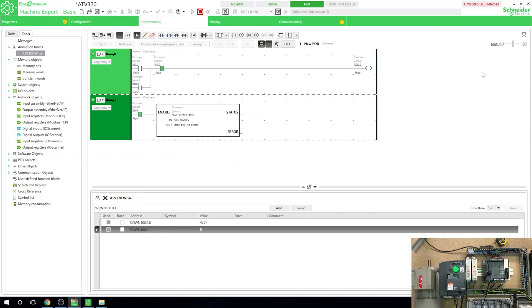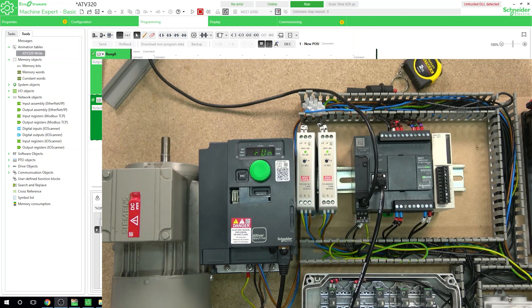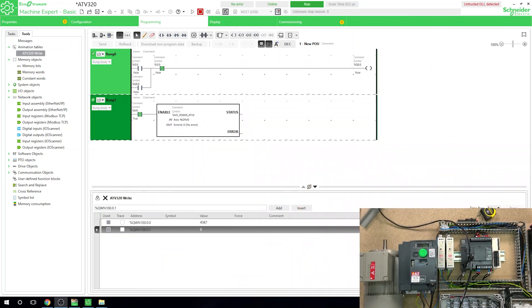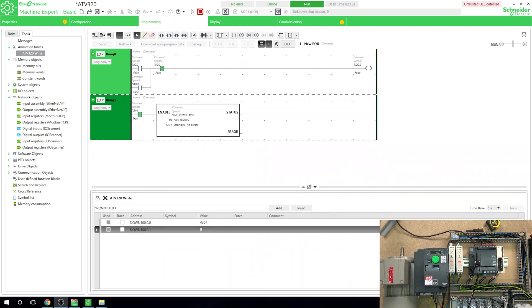We'll put the controller into run mode, then go into the programming and activate the M0 bit. If there are any communications errors, they'll show up here in the output error field — as you can see we have zero errors. Looking at the drive screen, it shows 'RUN' — it's ready to run, just waiting for a direction and frequency. Let's turn this off and it should return back to ready. That's done.